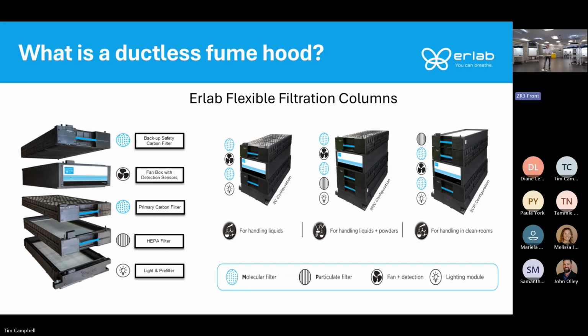So it's all modular. If you're not using powders, you don't need the HEPA filter. If you're, say, in a clean room and engineered space where you need to keep the particle count in the space, you can put a HEPA filter on the exhaust side of the carbon filter just to capture any minimal carbon dust that may be released.